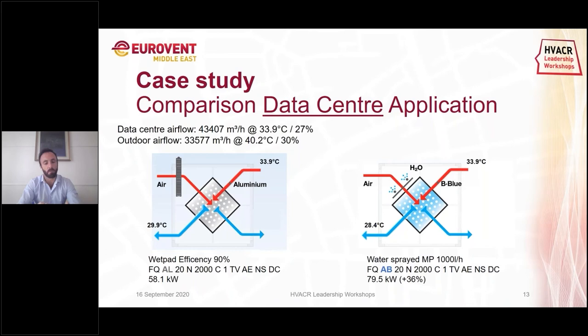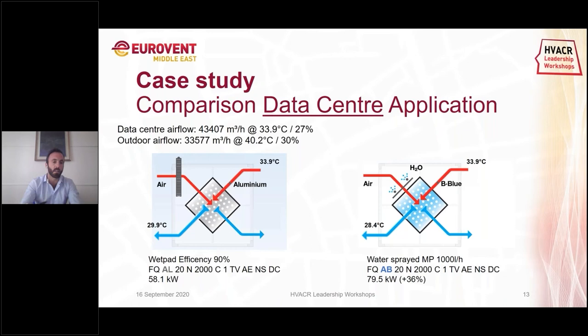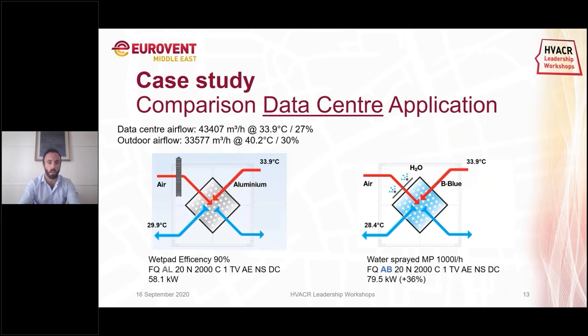We will now go through two case studies that are quite different from each other: the data center application, which is an industrial application, and the hospital application. These two are quite different. In the data center application, the system is a closed loop — the air of the data center circulates in a closed loop using always the same air — while the air that is wetted is the outdoor air, which we take from outside, cool, humidify, and then exhaust. It is important to keep the data center system tight and closed.